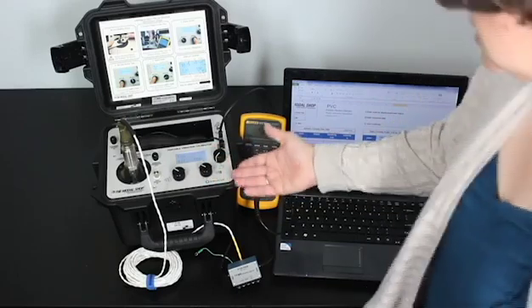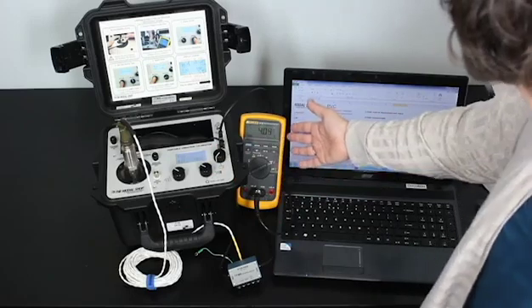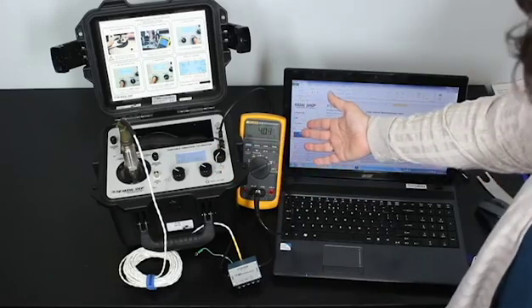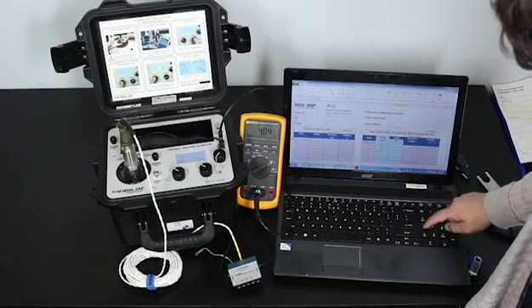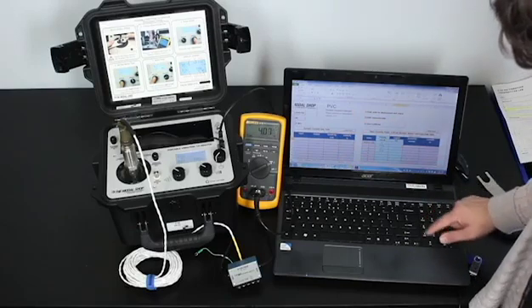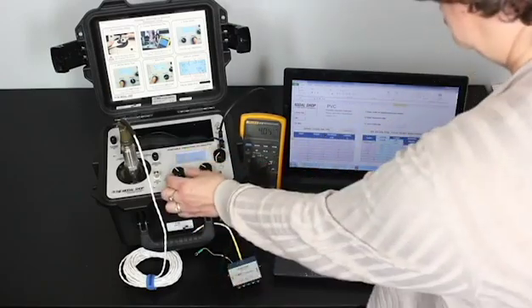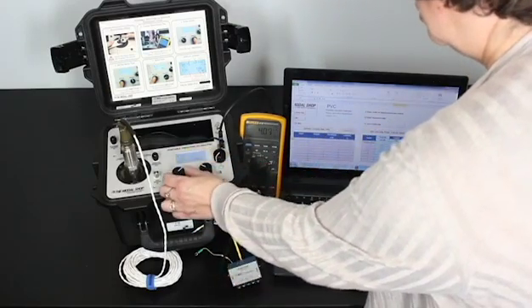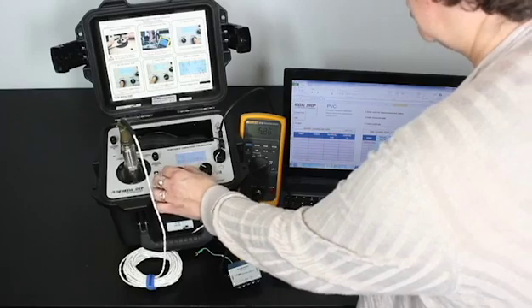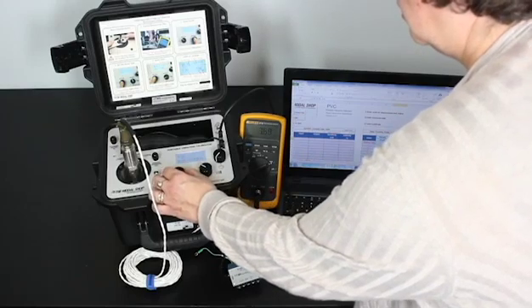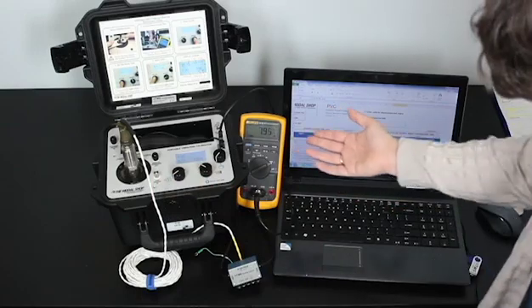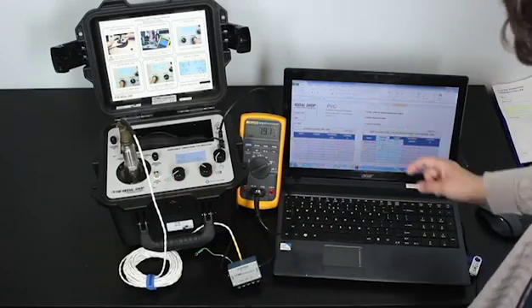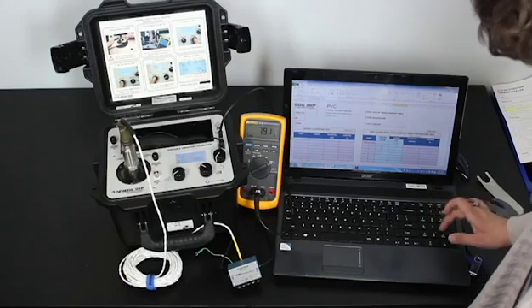So this is our first test point, and we can take a look at the multimeter and read that it says the output is about 4.04 milliamps. Now we'll adjust the amplitude to 0.25 inches per second peak. And we can see our response is 7.91 milliamps.